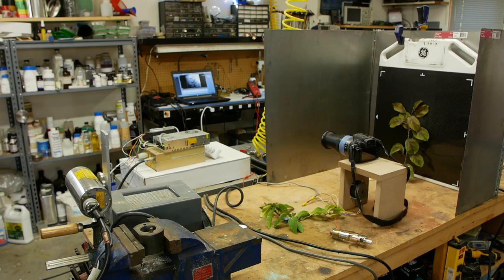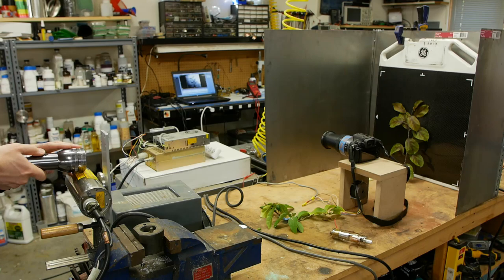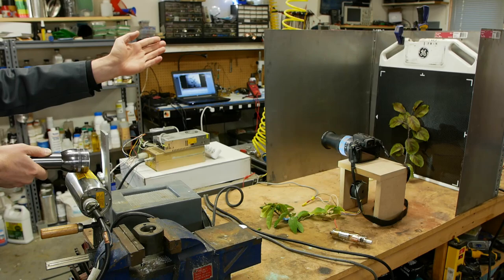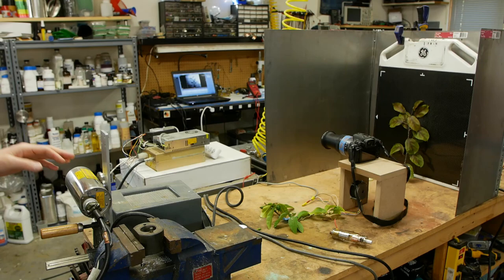Here's the whole setup. We've got the X-ray tube here, the object and the sensor. I use the computer to sequence this whole thing, turn on the X-rays, start an image acquisition at the panel. About 5 seconds later, the image is acquired. Shut off the X-rays and then wait a minute or two for the next frame. And most of those sequences that you saw were 200 or 300 frames long so that they would run for 5 or 10 seconds at 30 to 60 frames playback speed.